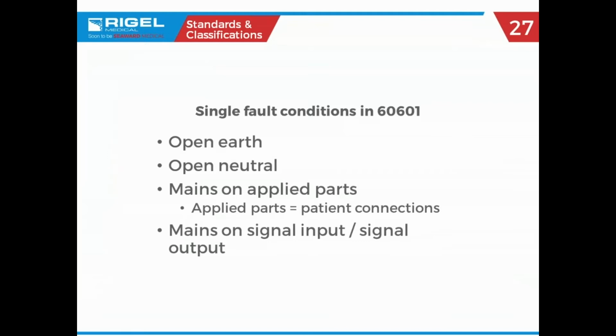Not that this ever happens, but there is a tendency sometimes not to unplug something by grabbing the nice thick part. Quite often it is unplugged how? And not always straight, sometimes at an upward angle. And since the ground pin is the last pin that exits the socket, and that's by design, because you want that to make first and break last, the ground pin breaks off, falls off. Single fault condition then is open ground. So when we do electrical safety testing, we always talk about single fault conditions.